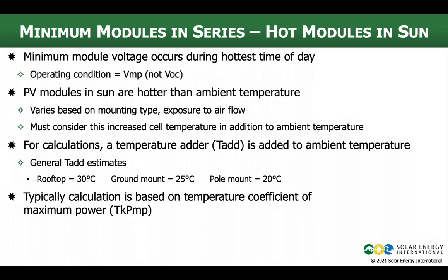Well, we know that the effects of temperature, while not limited to voltage, are primarily on voltage. It has a dramatic effect on voltage, the change in temperature, like about 1/3% for VOC. And the effect on short circuit current is very minimal. So minimal that we don't even really worry about it for the most part. It's almost zero.